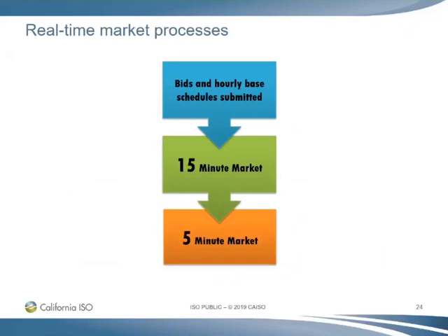In our real-time unit commitment process, the ISO makes final decisions on resource commitments to adjust the day-ahead schedule. Inputs into the real-time market include the day-ahead results, master file, real-time system information, supplemental energy bids, outage information, and transmission line information. The market results generate real-time dispatches, ancillary service awards, and startup or shutdown instructions via our automated dispatch system. These instructions are sent every 5 minutes.